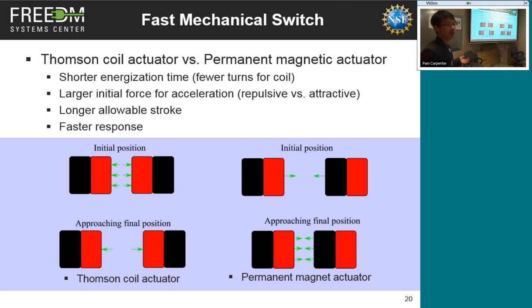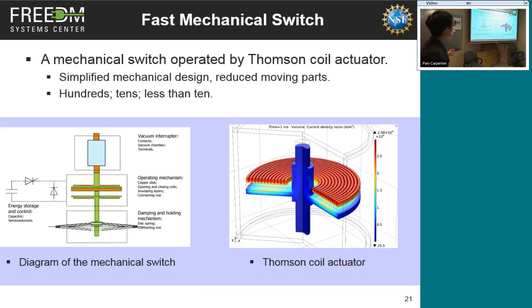But the Thomson coil is based on repulsion force, so you can put them very close at the beginning, and then the force is larger, giving faster acceleration. That's one of the key differences between them. I summarized that difference: the Thomson coil has shorter energization time, though that has nothing to do with this - it has to do with our coil design. It also has a larger initial force, which allows longer travel and a faster response. So we plan to pursue this Thomson coil actuator.